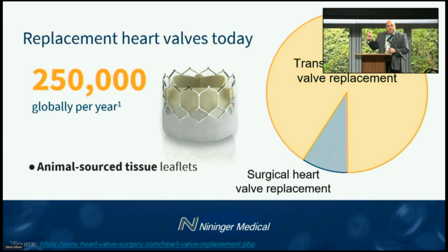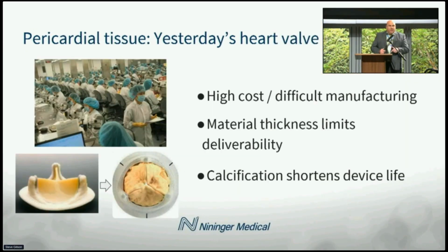The valves, as the one you see up here, are normally made with leaflets derived from animal tissue. That presents some challenges. That pericardial tissue is yesterday's technology. To harvest it, to treat it, to install it into the valves takes a lot of time and effort. The material itself isn't very uniform, and its thickness prohibits the catheters from getting smaller and smaller. Calcification is a reaction where the body ends up making the leaflets stiffer, and by making them stiffer, it actually makes it harder for the valve to work, and it shortens the valve's life cycle.